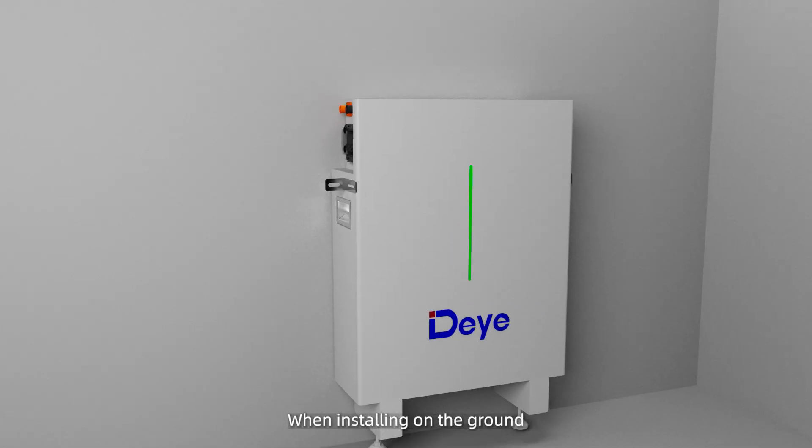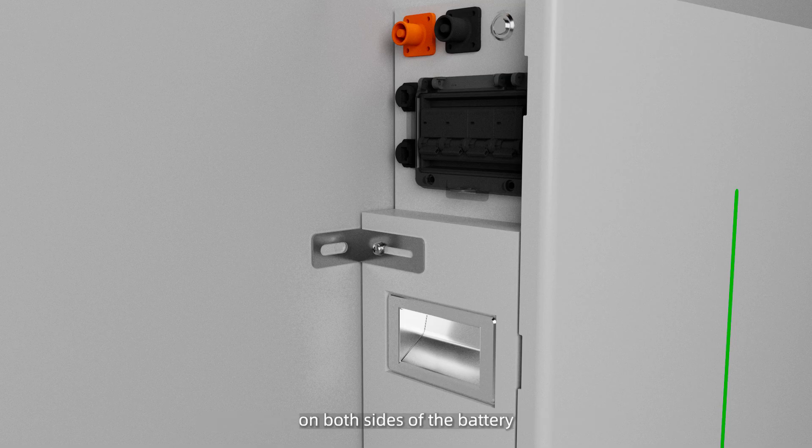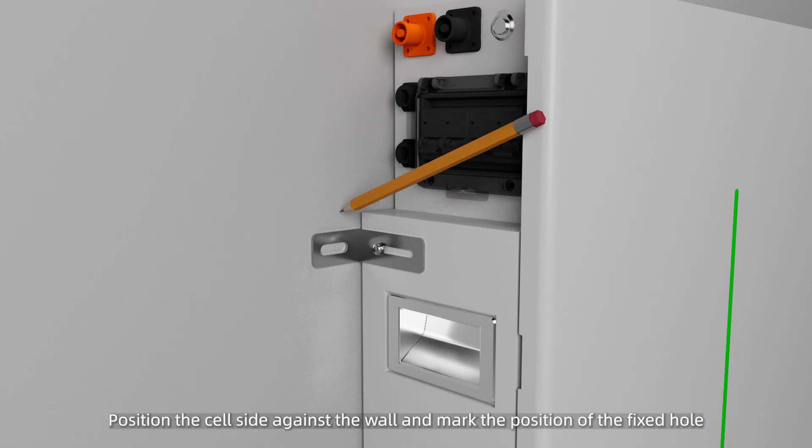When installing on the ground, use two M6x10 screws to fix the left and right fixing gears on both sides of the battery. Position the cell side against the wall and mark the position of the fixed hole.